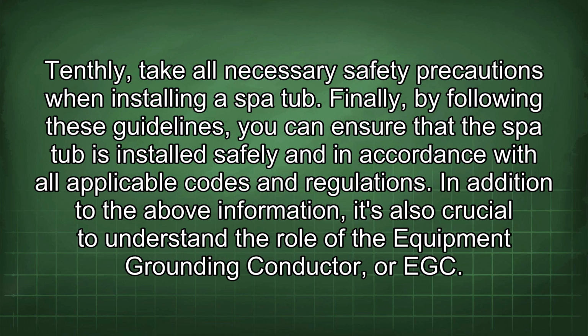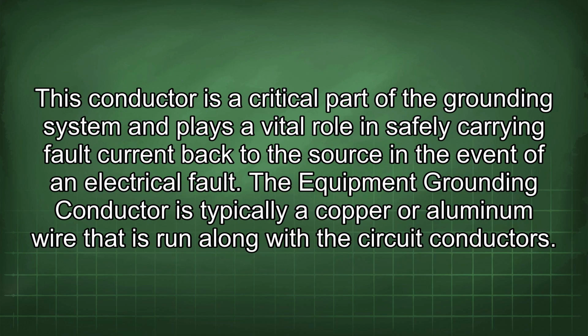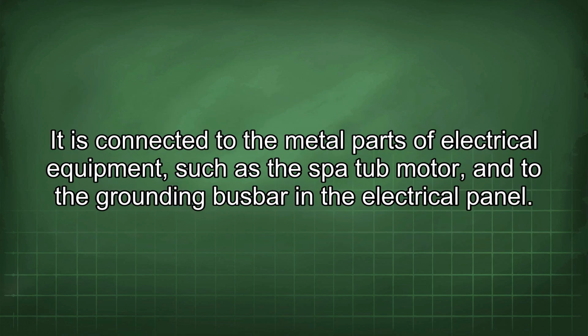grounding conductor, or EGC. This conductor is a critical part of the grounding system and plays a vital role in safely carrying fault current back to the source in the event of an electrical fault. The equipment grounding conductor is typically a copper or aluminum wire that is run along with the circuit conductors. It is connected to the metal parts of electrical equipment such as the spa tub motor and to the grounding bus bar in the electrical panel.